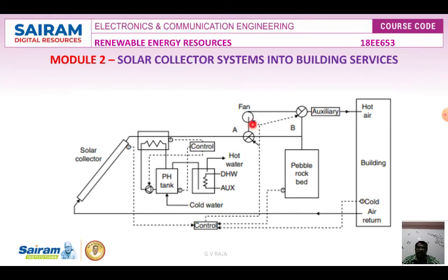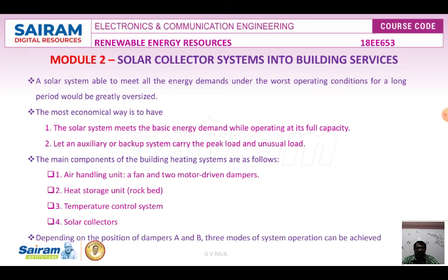In the second mode — damper A is open, damper B is closed — solar heat is collected but no space heating is required at that time. The fan blows the solar-heated air through the rock bed for thermal storage.